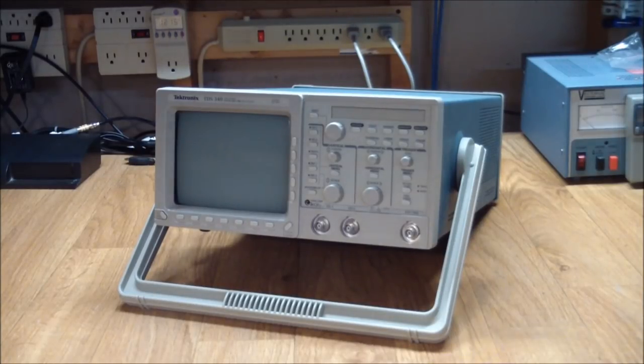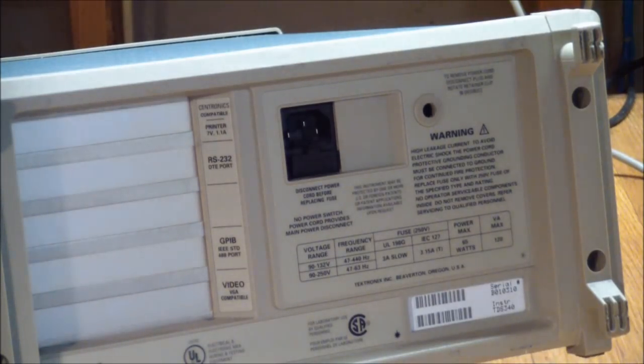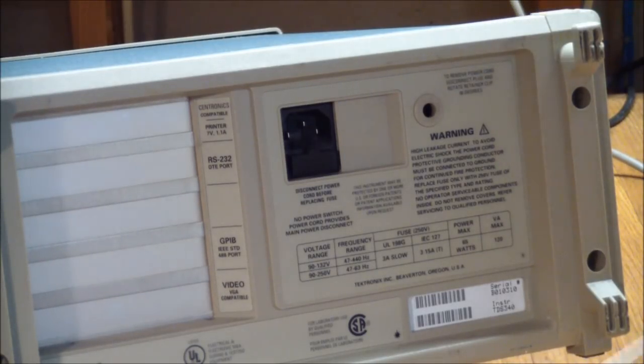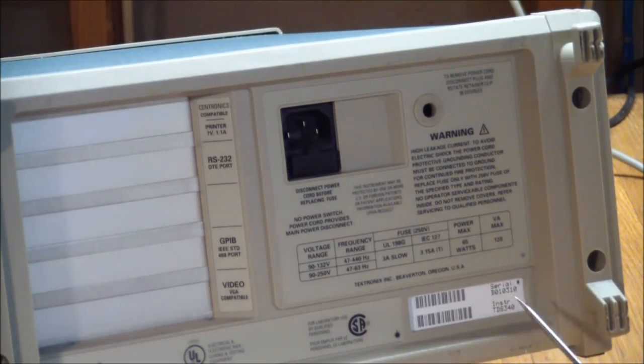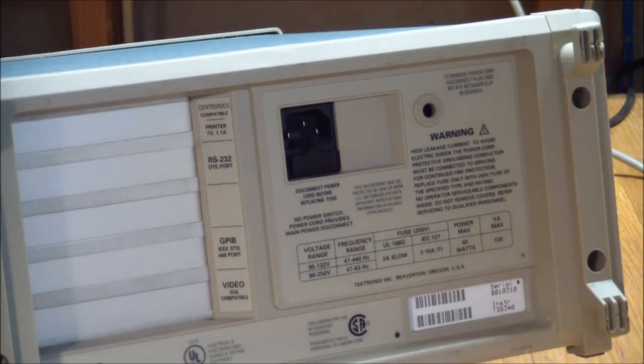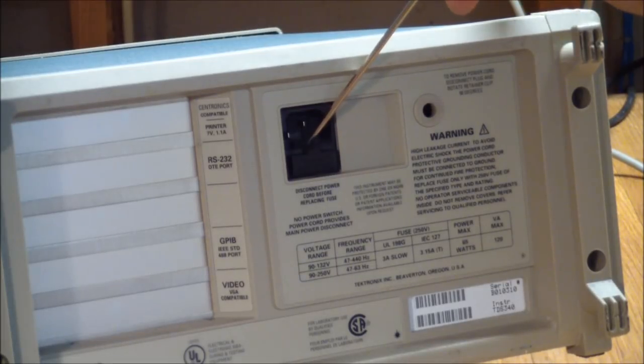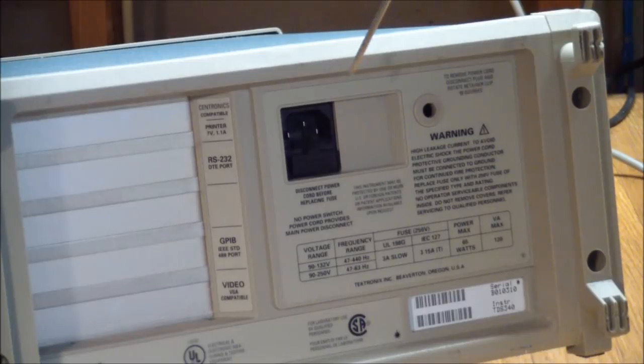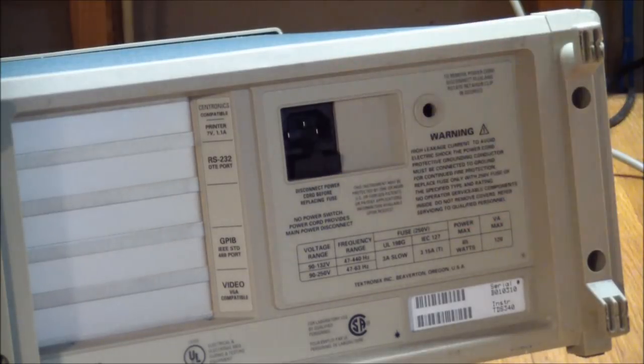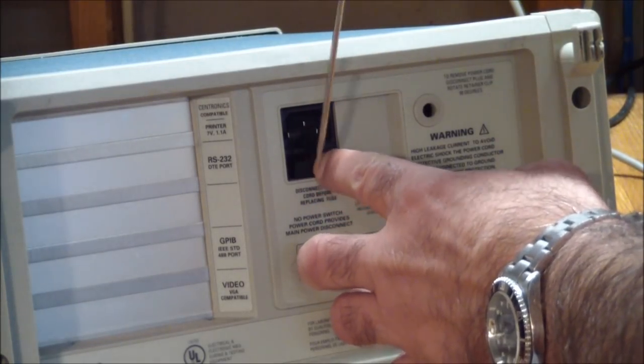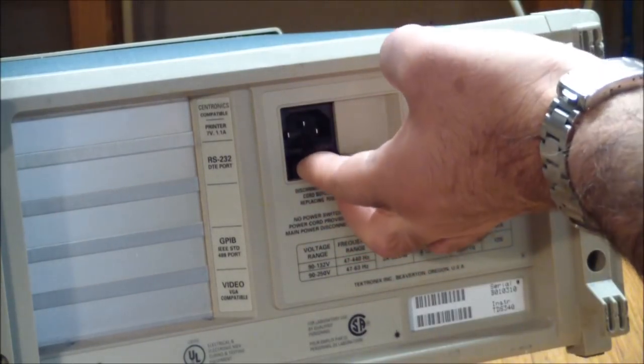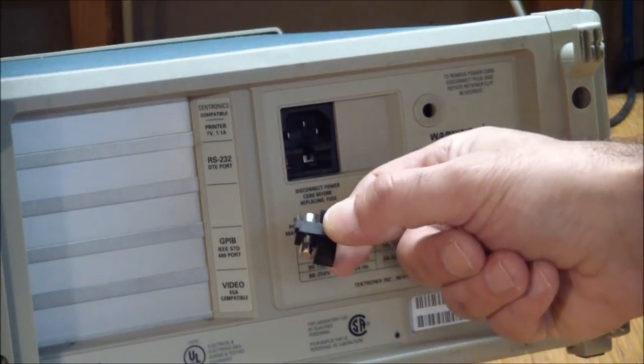So let's do the obvious and check the fuse. To get out the fuse should normally be an easy thing and even the service manual tells you there's a round fuse plug you just unscrew. But this one has that little sliding drawer underneath the IEC connector and there's a slot here that you basically have to get a small screwdriver in to pry the fuse holder assembly out. Which I've done. It's made of plastic so you've got to be careful not to mark it too much. Now it doesn't even want to come out the rest of the way. And here we go.